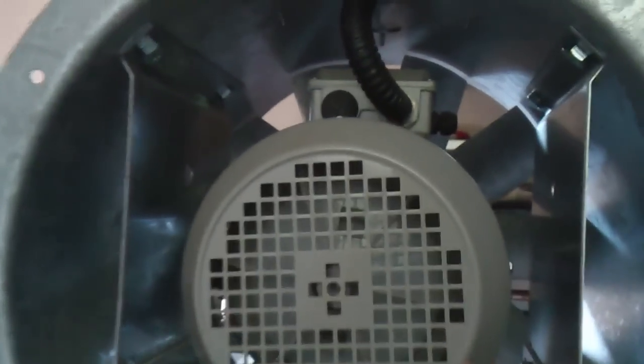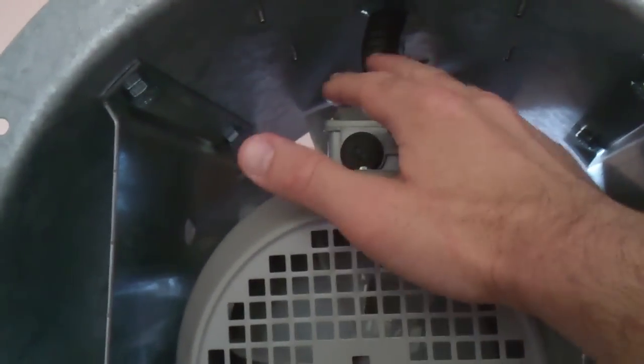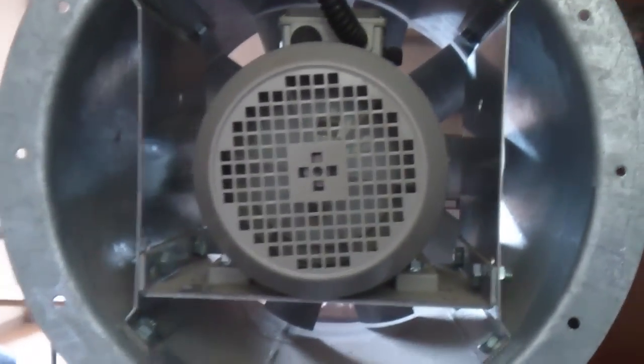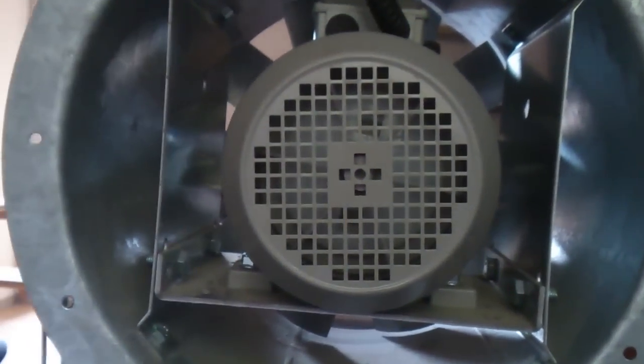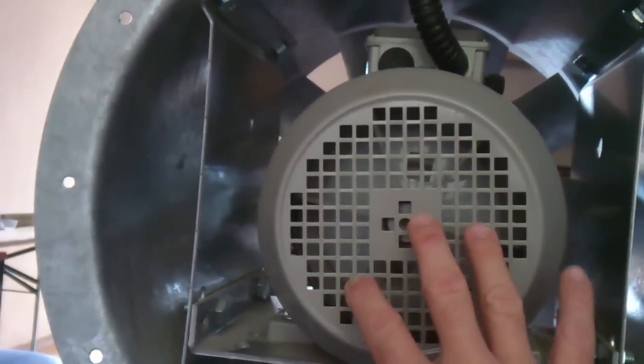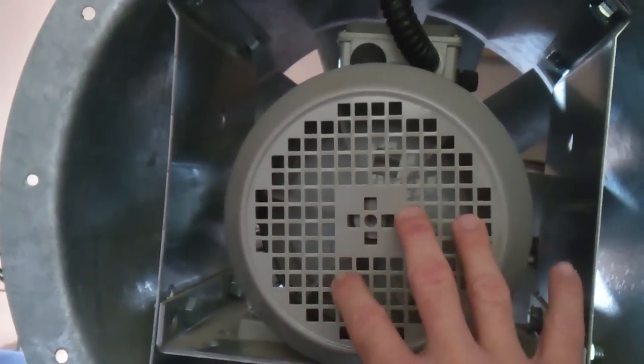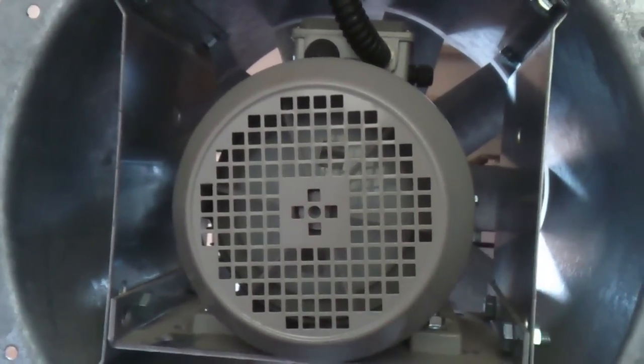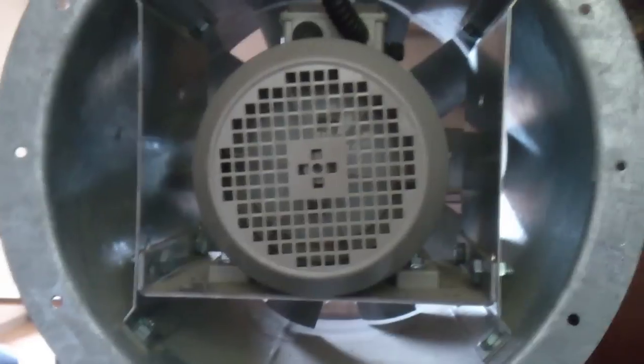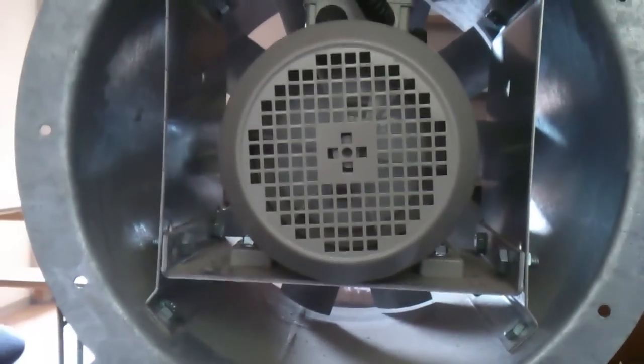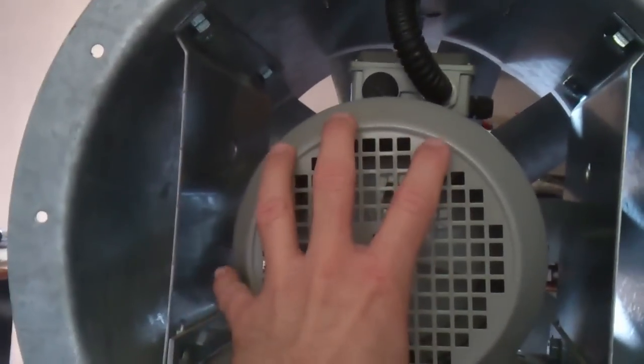You can imagine how much turbulence takes place around here. I think getting a smaller motor and optimizing your motor support would do wonders to your fan performance and fan efficiency.